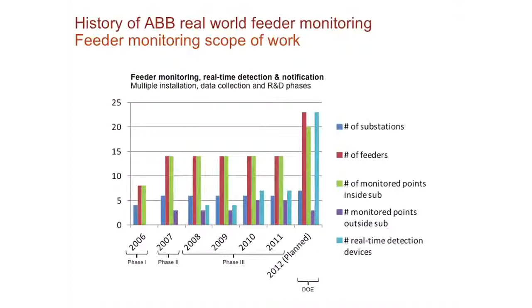Then in phase 3, we expanded the number of substations, the number of feeders, the number of monitoring points inside the substation, and outside the substation. Then in 2008, because of that first agreement, we put in an actual real-time detection device for incipient cable faults, underground cable faults. That's been running ever since, and we've been expanding on that.